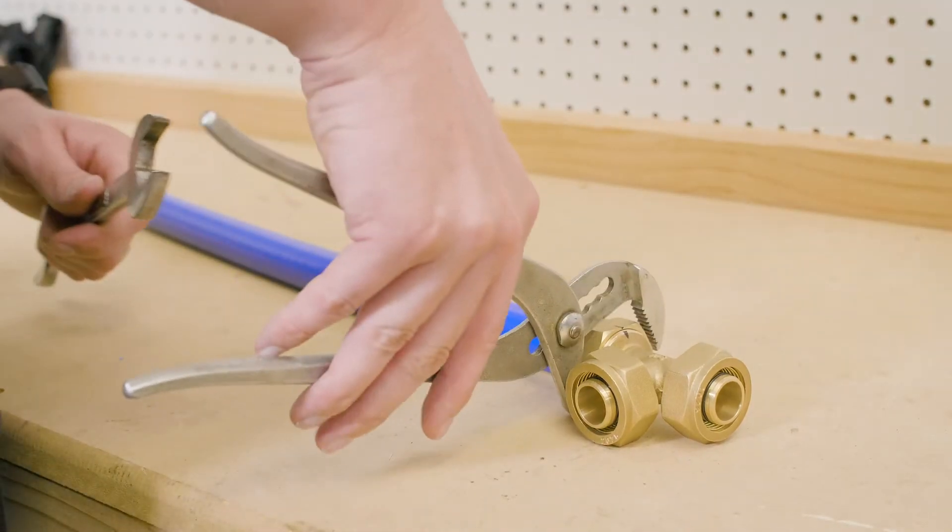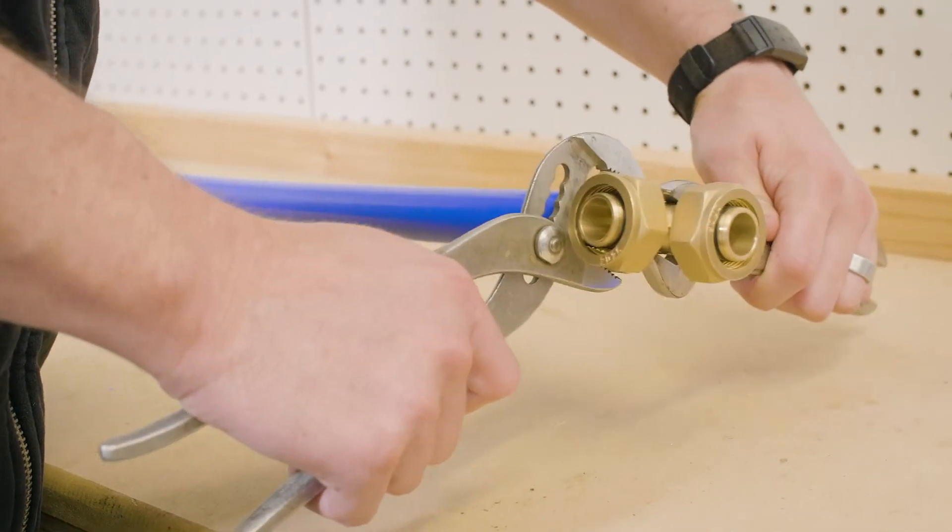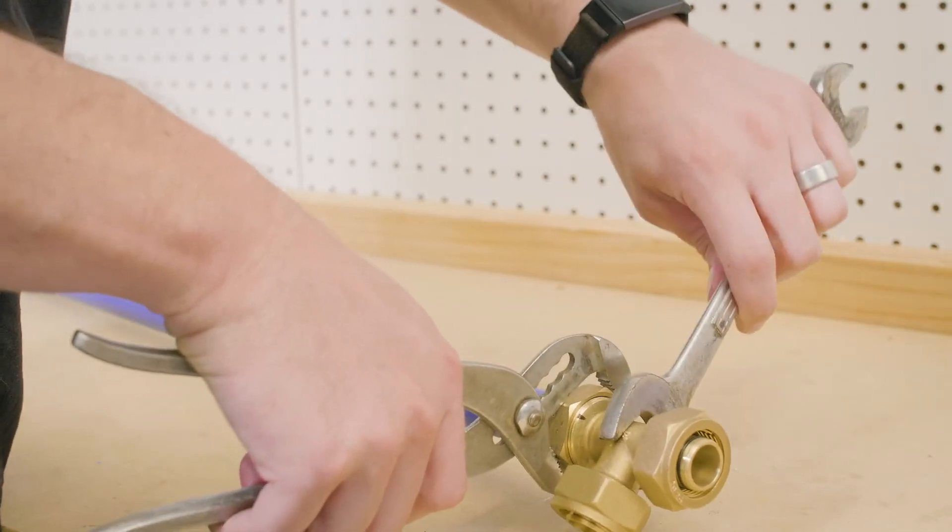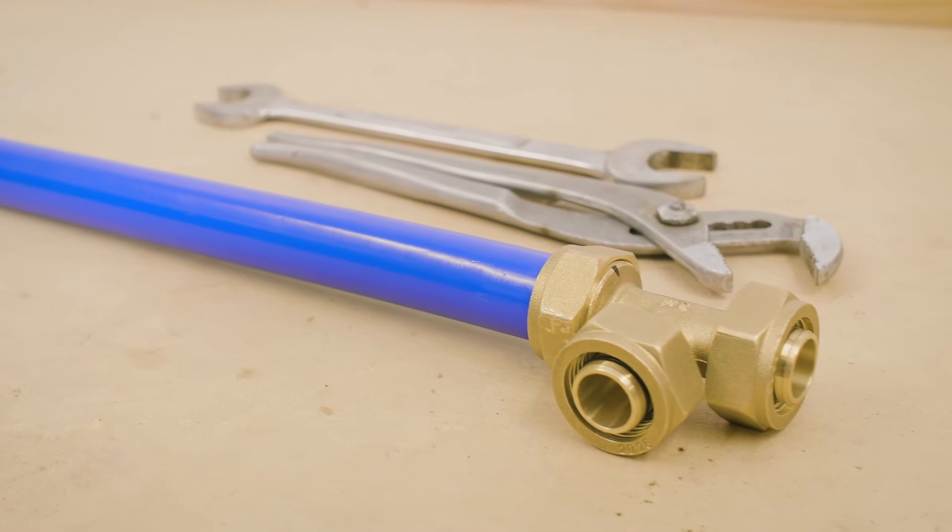With a wrench, use the reference mark as a guide to tighten the fitting three-quarters of a turn or until tight. Note, over tightening may cause damage to the pipe.